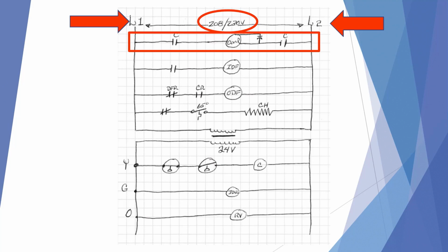On the first line we have the compressor, and it is controlled by the C, or the contactor coils. When the coil of the contactor is energized, the compressor will run as these contacts will close. On the second line we have the indoor fan motor. It is controlled by a set of contacts that when energized, our indoor fan motor will run.